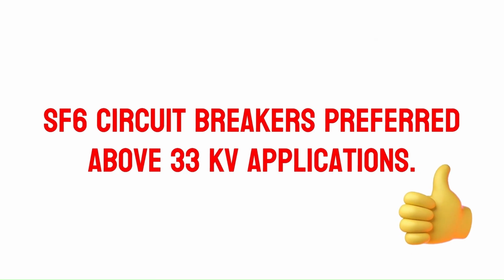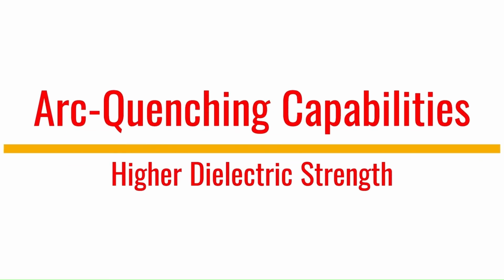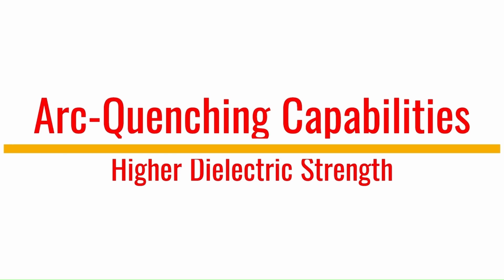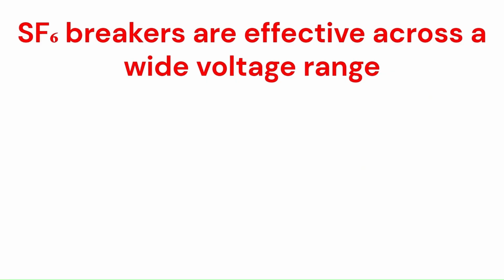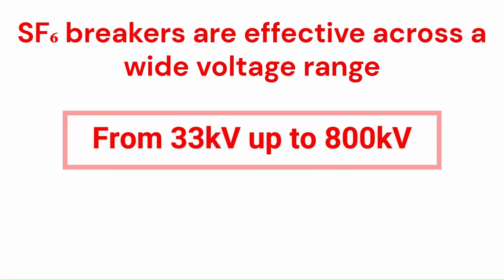Due to all these limitations, for the systems operating above 33 kV, SF6 circuit breaker offers a more reliable and cost-effective solution. Because SF6 gas has superior arc quenching capabilities and higher dielectric strength than vacuum at high pressure. SF6 breakers are effective across a wide voltage range, that is from 33 kV to 800 kV, and provide better performance in very high voltage systems.